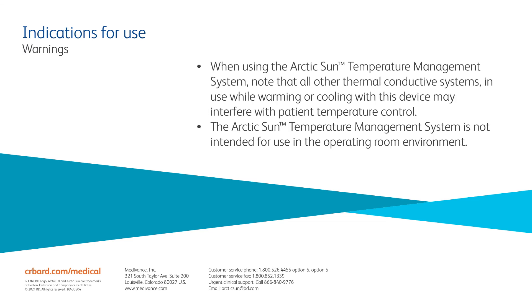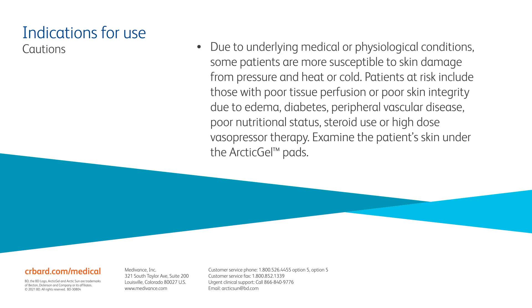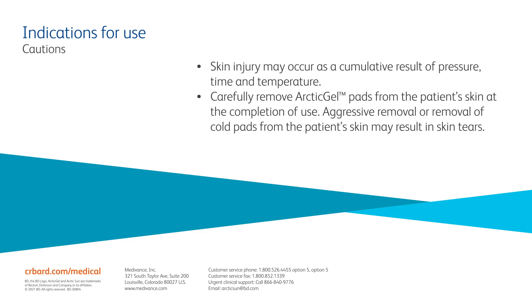When using the Arctic Sun Temperature Management System, note that all other thermal conductive systems in use while warming or cooling with this device may interfere with patient temperature control. The Arctic Sun Temperature Management System is not intended for use in the operating room environment. Due to underlying medical or physiological conditions, some patients are more susceptible to skin damage from pressure and heat or cold — including those with poor tissue perfusion or poor skin integrity due to edema, diabetes, peripheral vascular disease, poor nutritional status, steroid use, or high-dose vasopressor therapy. Examine the patient's skin under the Arctic gel pads, as skin injury may occur as a cumulative result of pressure, time, and temperature. Carefully remove Arctic gel pads from the patient's skin at the completion of use.